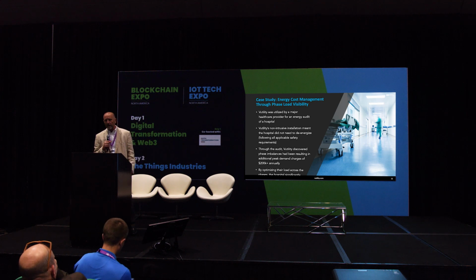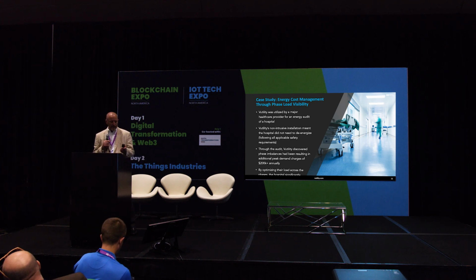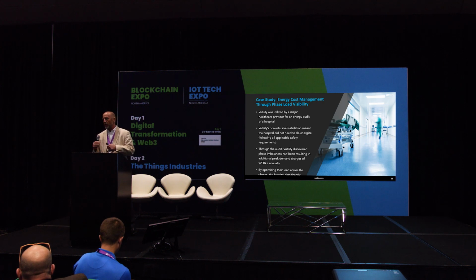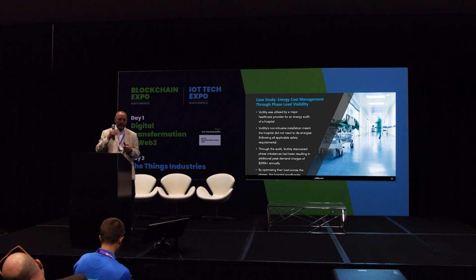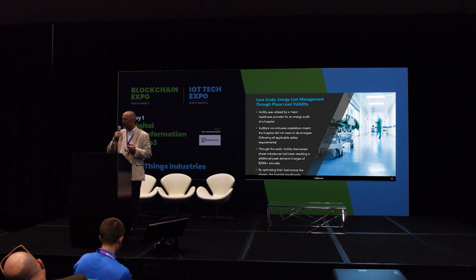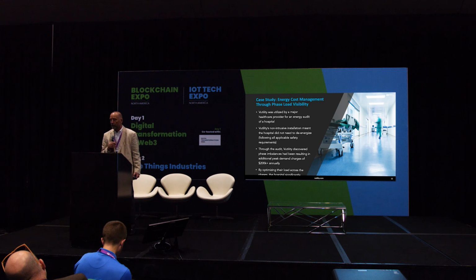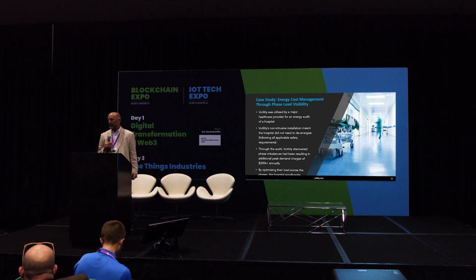Through the audit, one of the things we found was a severe phase imbalance. Their energy provider at this hospital charges based upon the power used in the highest phase, and I'll show you an example from our building at our headquarters. That was costing them $200,000 plus a year because of those added charges. So they've now gone back in, rewired their branch circuits, and leveled out and balanced their load.